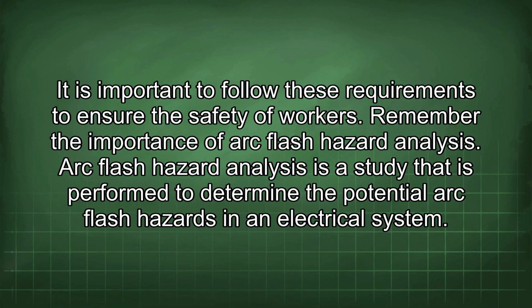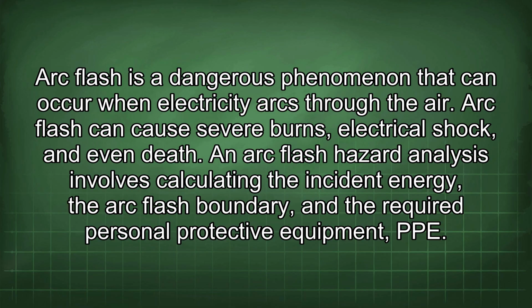Arc flash hazard analysis is a study that is performed to determine the potential arc flash hazards in an electrical system. Arc flash is a dangerous phenomenon that can occur when electricity arcs through the air. Arc flash can cause severe burns, electrical shock, and even death. An arc flash hazard analysis involves calculating the incident energy, the arc flash boundary, and the required personal protective equipment (PPE).